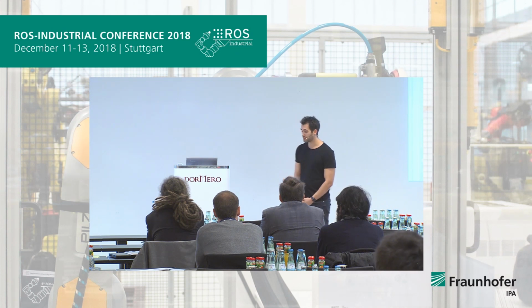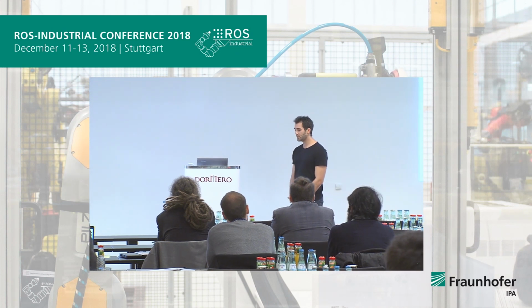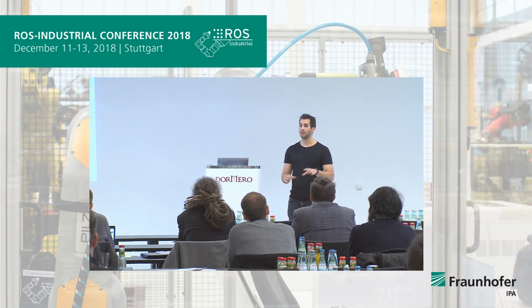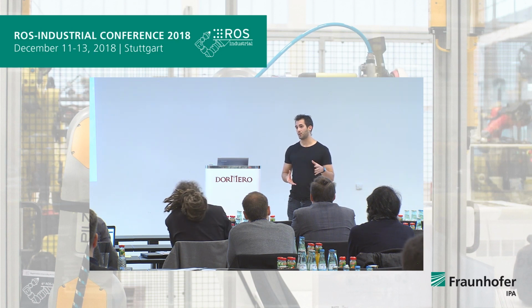That's a very good question. Thank you. So we did a lot of research at the very beginning, when we were working with DARPA, evaluating different, let's say, field buses. We tried EtherCAT, we tried Profinet, we tried CAN. The point is that our vision of modularity had certain restrictions, let's put it that way. We wanted a channel with high bandwidth, so we wanted to go, if possible, gigabit. With EtherCAT, you cannot do that.